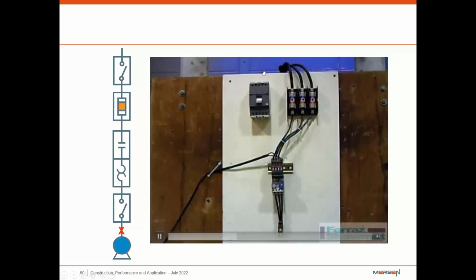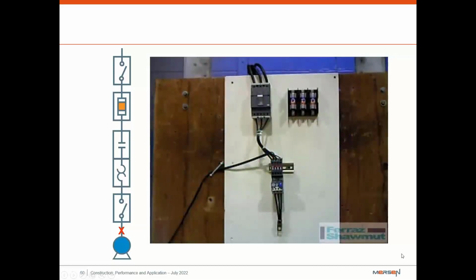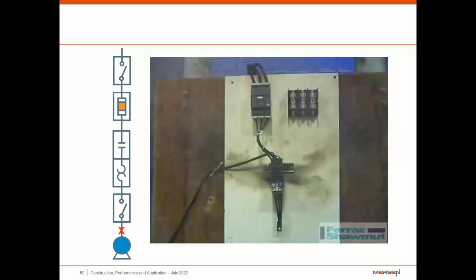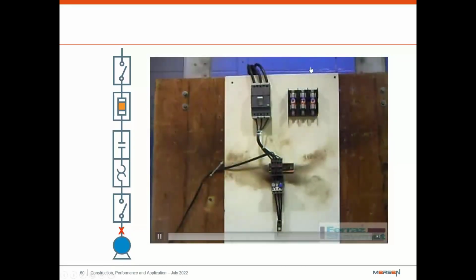So now, getting into some actual videos on this, I'm just going to go ahead and let these play. This is going to be your type 1 protection versus type 2 protection. As you can see, notice that there's going to be a flash on the fuses themselves in this application. Right now what we're looking at is the type 2 protection, which will allow both of these to operate correctly. Type 1 protection means that this has to open at all costs, and there's going to be damage to some of the equipment. This is a proper UL application. This is with a breaker in place and an overload relay down below, and that is considered a proper UL application. With fuses, the fuses will protect to make sure that the overload relay does not explode.